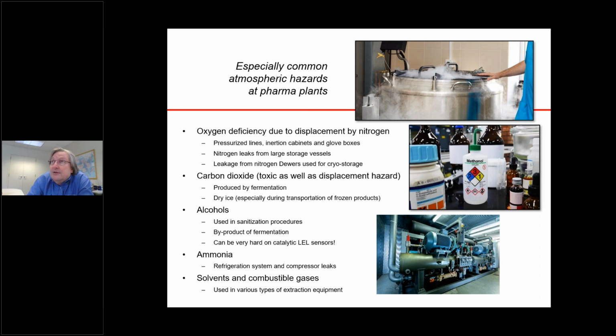Ammonia. You use a lot of ammonia in refrigeration systems that run through pharmaceutical plants. You don't generally run your refrigeration systems off of the liquid nitrogen. It's just a little too dangerous. You use ammonia to cool down what is called brine, a liquid that is then pumped in pipes around the site or wherever you want the cooling to occur. And it's the brine that transfers the cold temperature to the ambient atmosphere. You recirculate the brine back to the countercurrent ammonia refrigeration system and compressor, and that's what's going on.